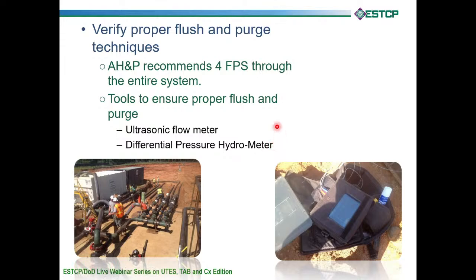Another good thing for commissioning agents to do is to verify proper flush and purge techniques through the GHX. AH&P recommends a minimum of 4 feet per second through the entire system, no matter the pipe size. So the tools that we would use to ensure proper flushing and purging would be an ultrasonic meter shown over here, also a differential pressure hydrometer that you could plug into the flushing pump and make sure your total flow is correct, or if you had a Venturi flow meter, you could plug in there and determine flow rate. But just anything to determine flow rate.